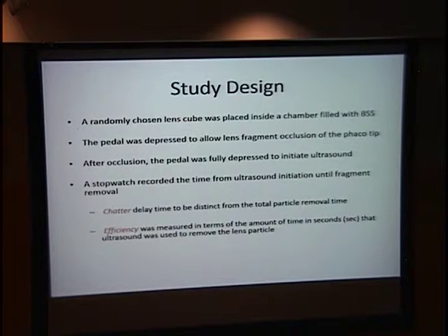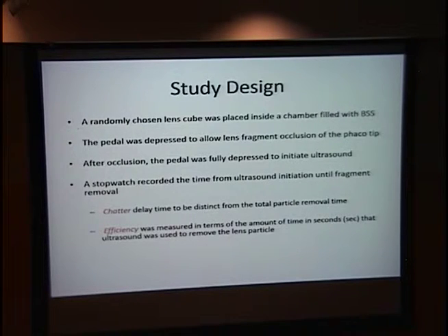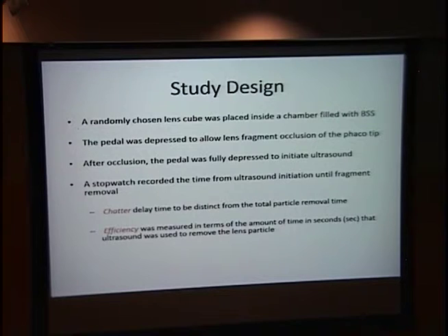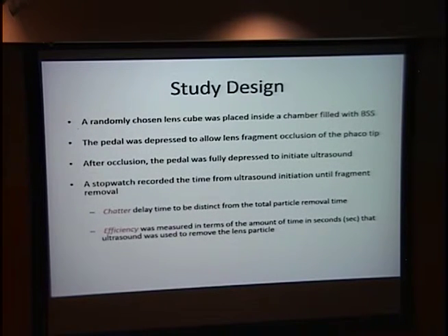Our study design is straightforward. We take the lens cube and fill it in a BSS chamber. We engage the pedal just enough to get the tip to be occluded with the nuclear fragment, and then after occlusion, we fully depress the pedal to activate the ultrasound. A stopwatch records the time of removal, and we also counted the number of chatter events — when the lens material removes off the end of the tip and we have to re-engage it. Chatter was a delay in time distinct from total particle removal; efficiency was measured by the amount of time required to remove the lens particle.